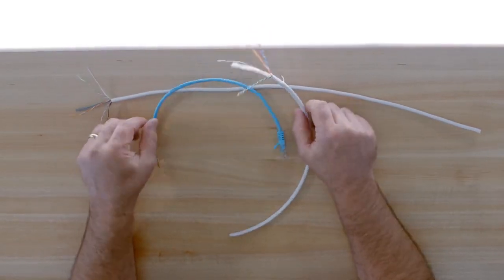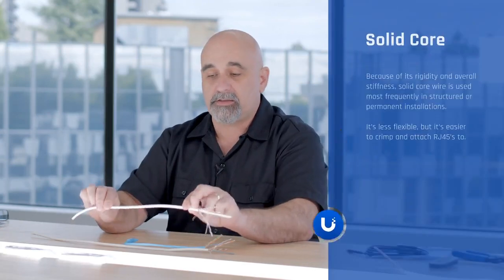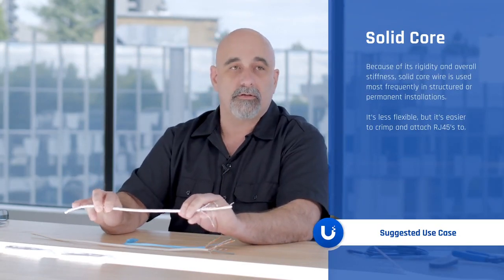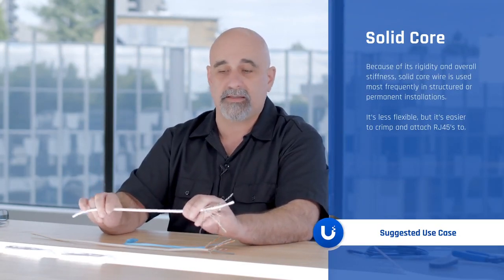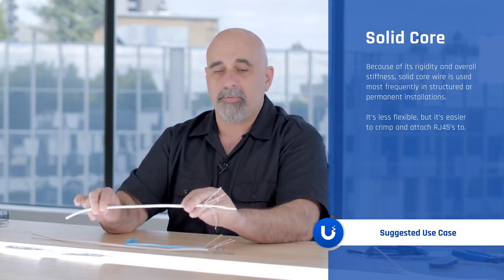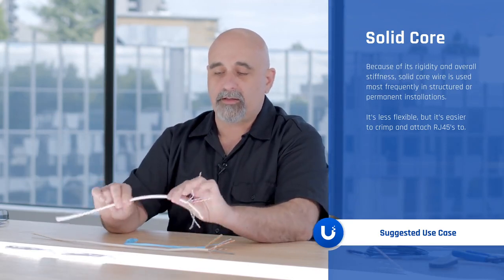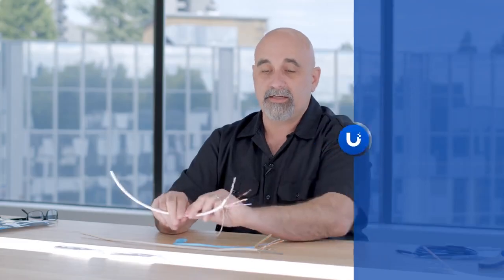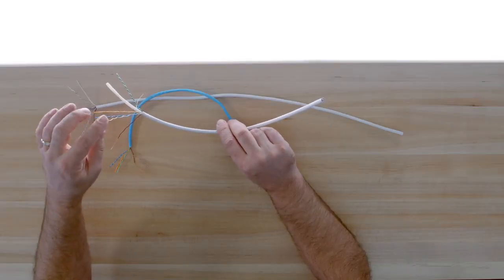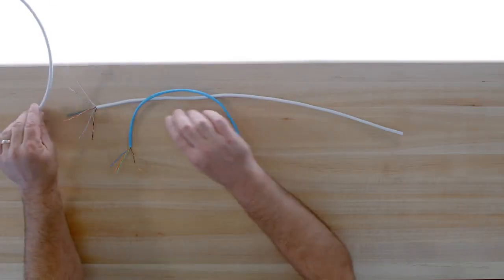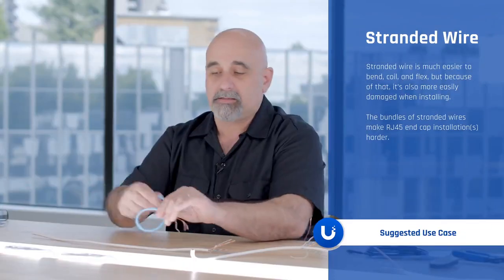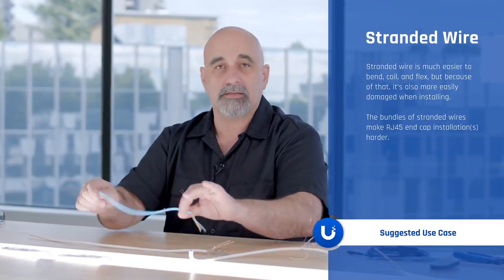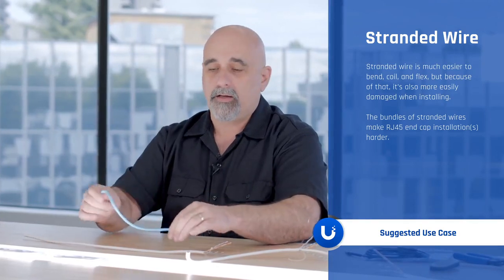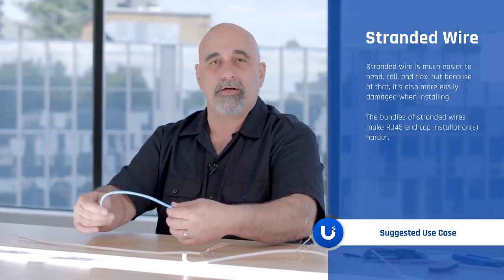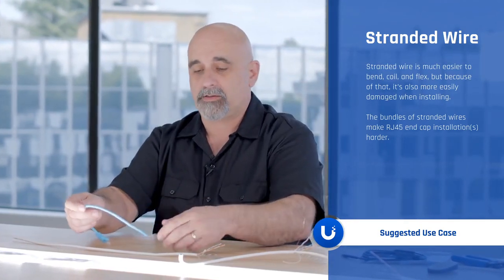Solid core wire is a lot stiffer, and it's used more in structured installations or permanent installations. It's a little bit harder to bend, but it's a little bit better for the interior installations, especially for crimping ends and putting on your inserts. Stranded bends a lot easier, it's a lot smoother, can coil up, but can be a little bit more damaged when you're pulling inside of walls, and it's a little more difficult in crimping.